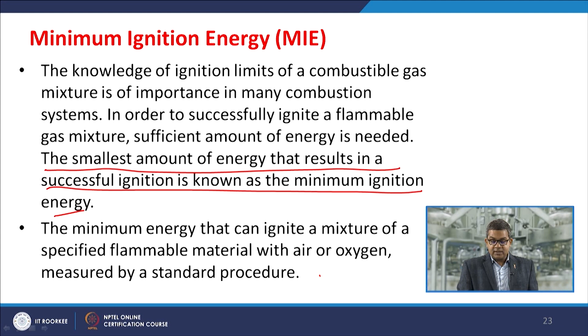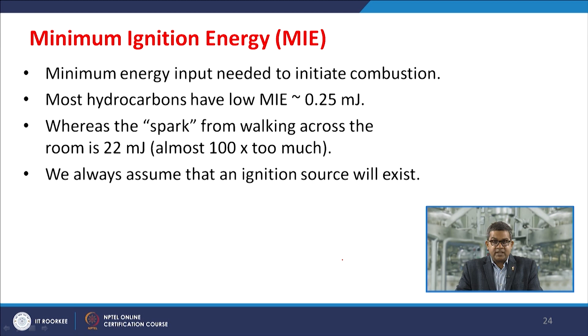In a single line, you can say it is the minimum energy input needed to initiate combustion. Most hydrocarbons have a very low minimum ignition energy, around 0.25 millijoule, whereas a spark from walking across a room is around 22 millijoule, almost 100 times greater than what is required. That's why whenever you visit a refinery or any hydrocarbon plant, it is always advisable not to wear shoes with nails or iron nails. So we always assume that an ignition source will exist. The only thing is that we need to minimize the impact of this source of ignition.